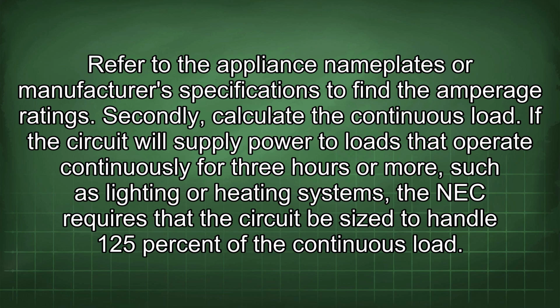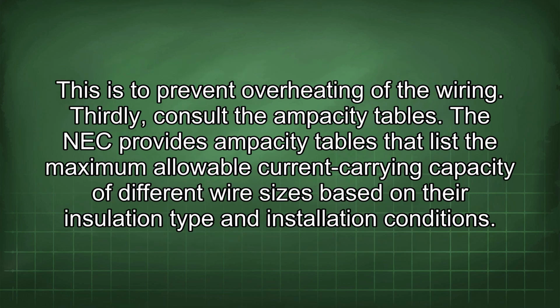Secondly, calculate the continuous load. If the circuit will supply power to loads that operate continuously for 3 hours or more, such as lighting or heating systems, the NEC requires that the circuit be sized to handle 125% of the continuous load. This is to prevent overheating of the wiring.